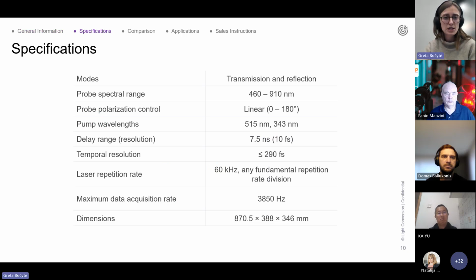Talking about specifications, we will have two modes in here, transmission and reflection, without any modules like a time-resolved fluorescence module or microscopy module. Here we will have only transient absorption in transmission and reflection. We will have quite a narrow probe spectral range, from 460 up to 910 nanometers. As I mentioned before, probe polarization control is linear. Pump wavelengths are from the harmonic generator, second and third harmonics.